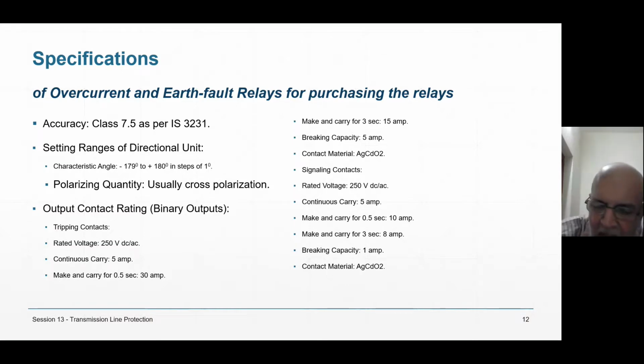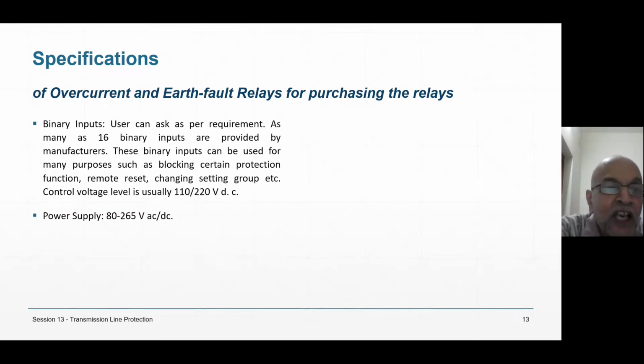This is binary outputs. Then there are binary inputs. Usually nowadays people give 16 binary inputs, but the functions of binary inputs are probably 50 or so. So you cannot use all the functions. Whatever functions you need, you have to configure. So binary inputs means 110-volt DC is to be given to a particular contact, and if you give that, certain things will happen. That means either the setting group will change, there are 6 setting groups in overcurrent relay, or the relay will block, some protection function will block, right?